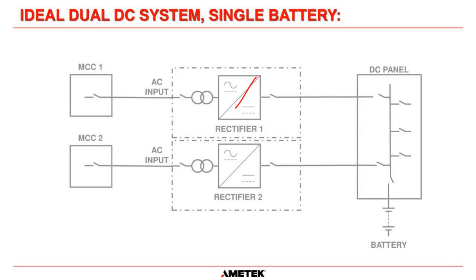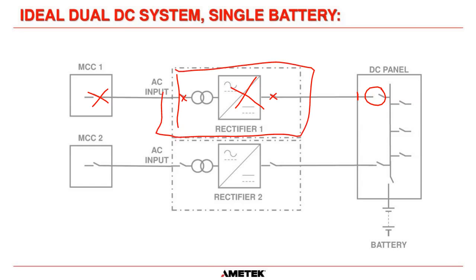Let's say, for example, rectifier 1 fails in this situation. What we can do is open this breaker here on the DC panel, and therefore that makes this point here volt free. Once we isolate the MCC, lock and tag out that, lock and tag out that, lock and tag out that, then we can actually take this whole rectifier out and replace it with a new one if necessary, and the power flow goes through here through rectifier 2 and keeps the batteries charged and your load circuits powered. So this gives us a huge amount of flexibility.